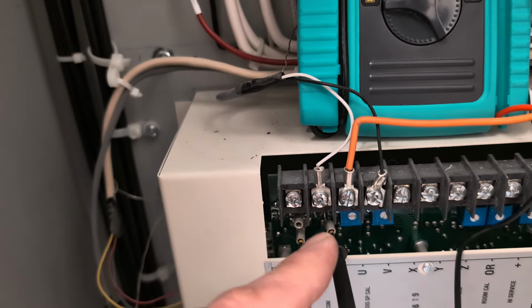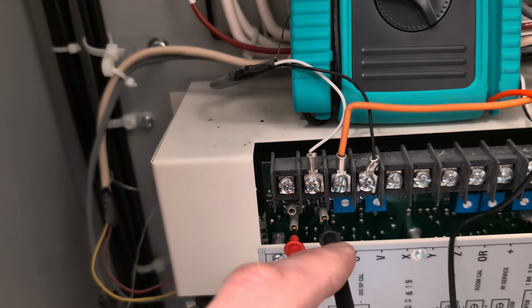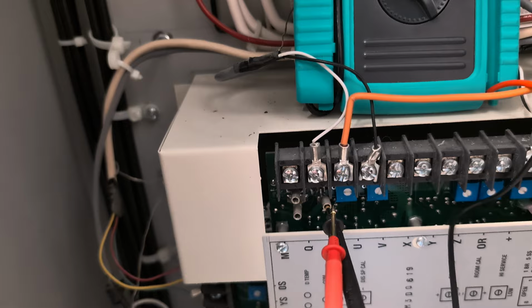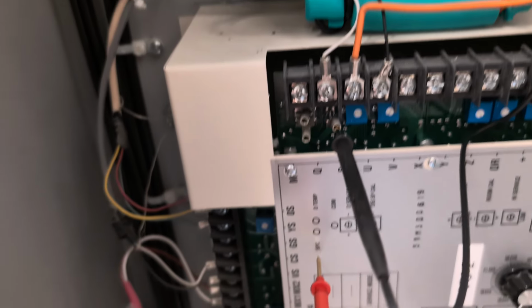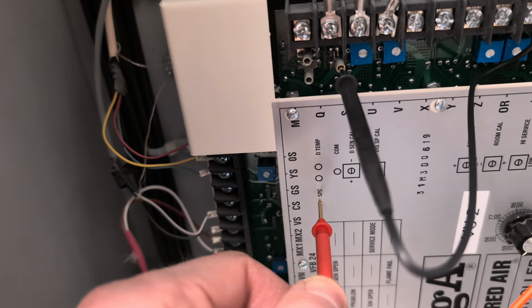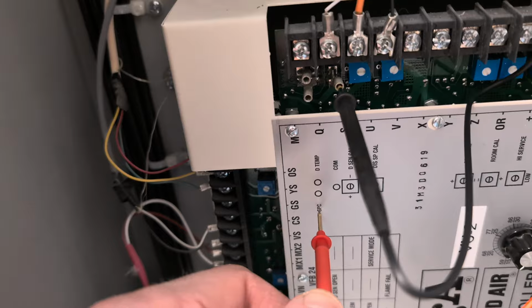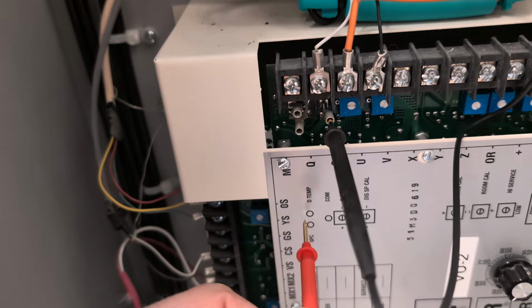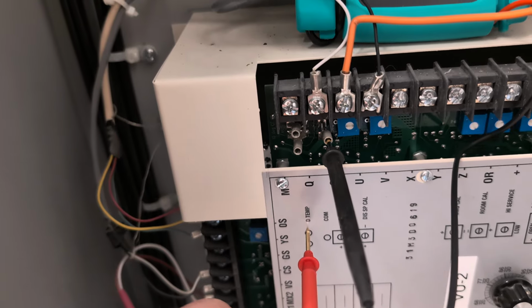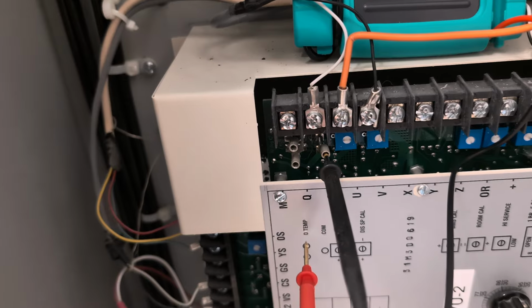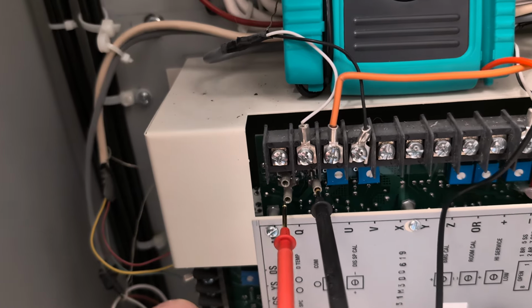So you can see these three ports here. This one is the COM, so this is common. And then as you can see here, this one says SPC, so this is your set point. This D temp is your discharge air temperature.